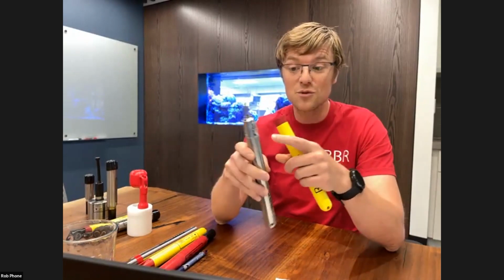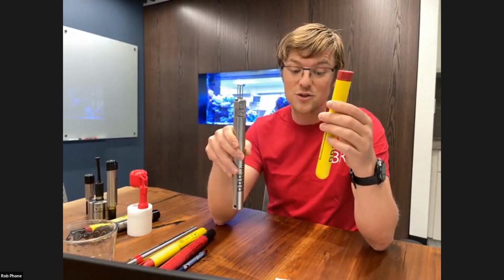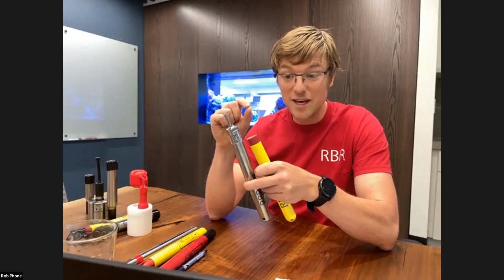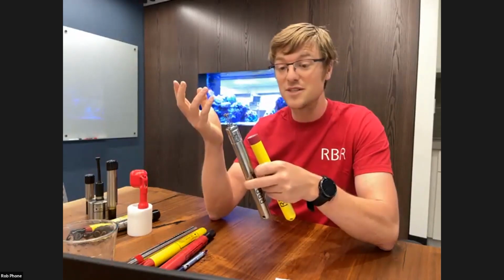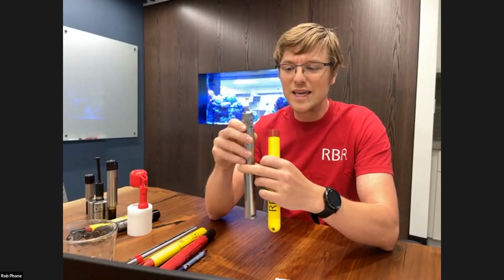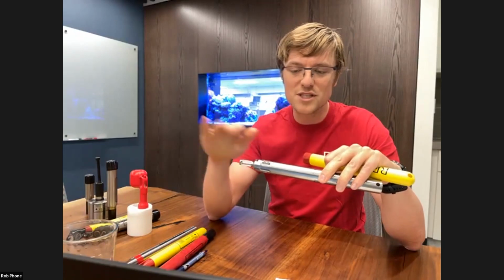The main difference for the very deep rated units versus the shallow rated unit actually lies in the crystal inside. So changing the thickness of that particular crystal changes the sensitivity to pressure. And they're quite robust. The damage one can do to these sensors is essentially if you've damaged the membrane.